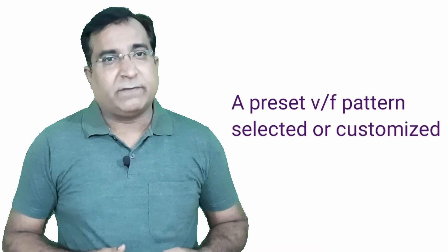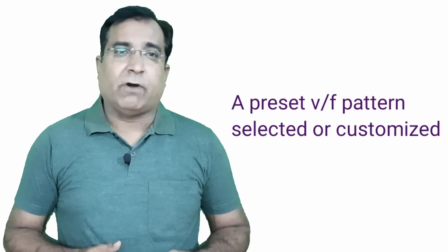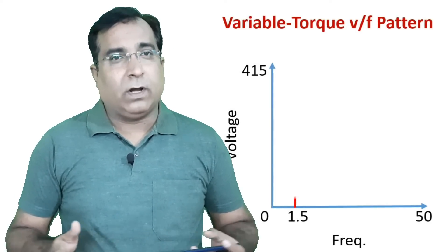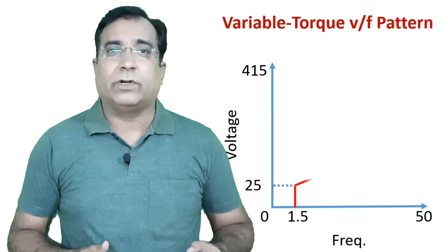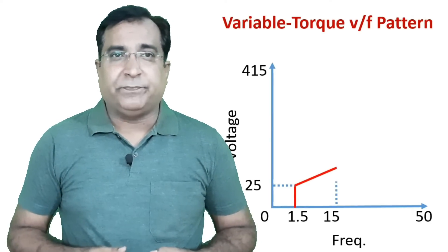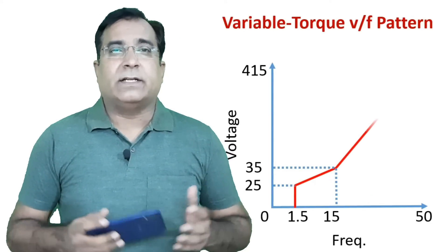There you will have to select the variable torque pattern or you can also customize V by F pattern as per your application requirement or need. This V by F pattern is nothing but a curve of ratio of voltage and frequency which follows a particular motor. The V by F pattern indicates how much voltage across the motor or torque required at a particular frequency. You can also select the preset and customize it.